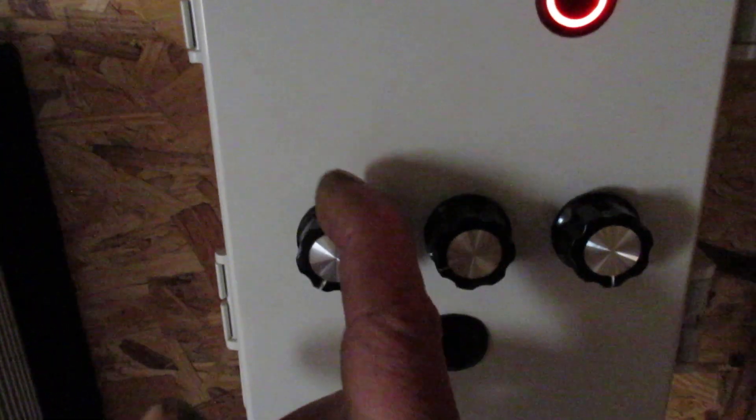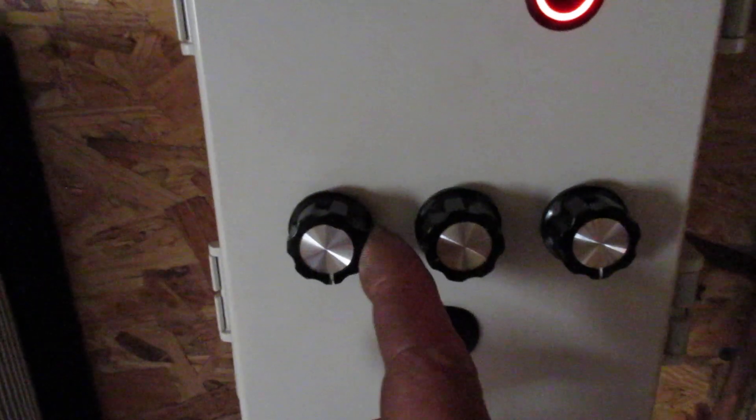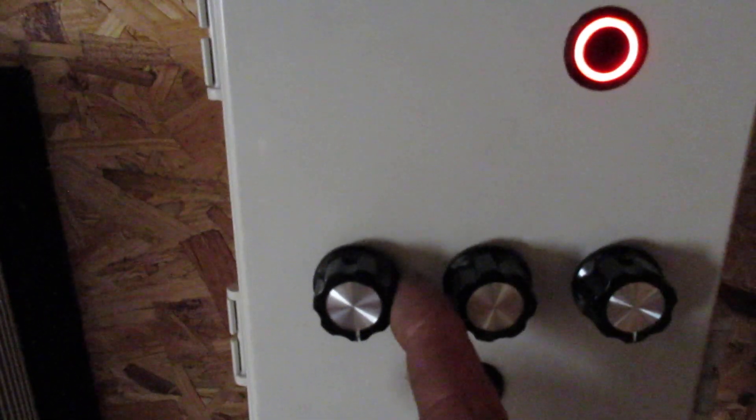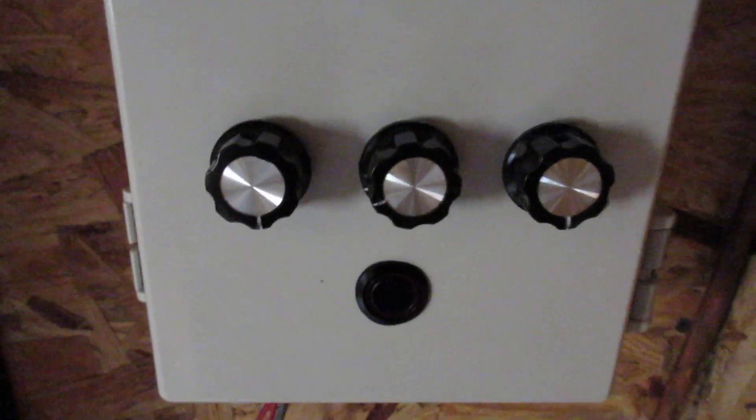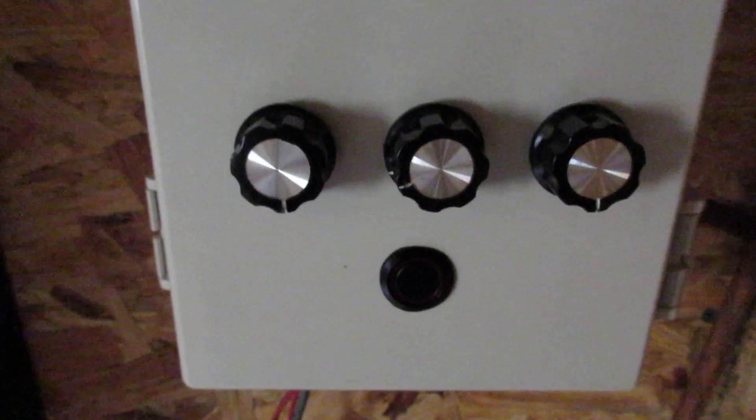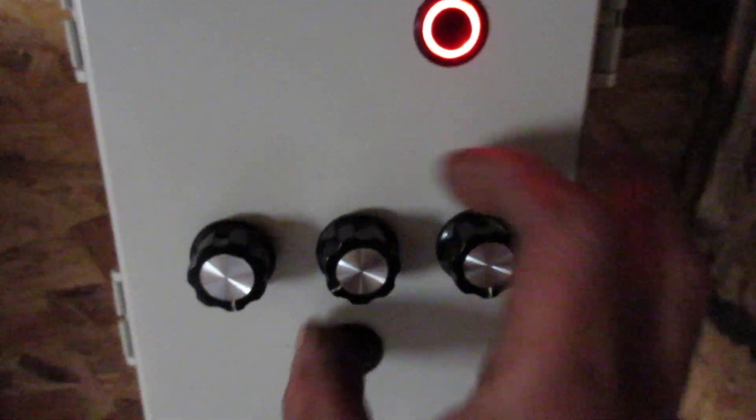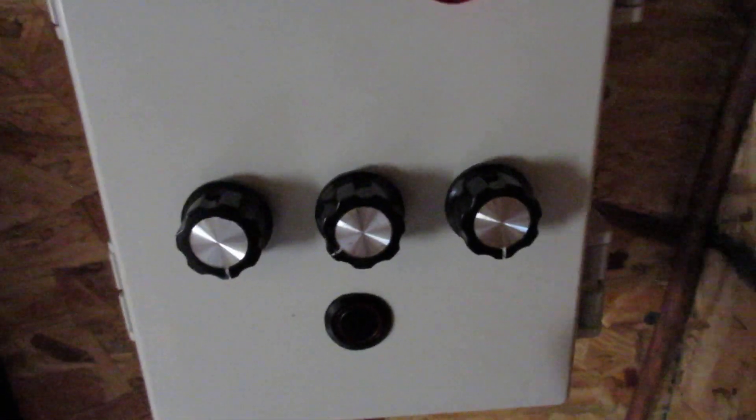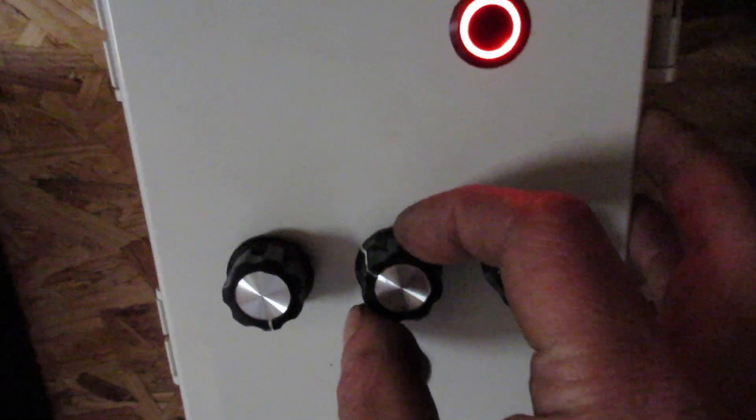But again, this one here is your choke position. So with this turned fully counterclockwise, the choke will be left fully open. So like in summer months, you may not even need to choke the generator, so you'll turn that all the way down. And then your duration - you could even shorten that. Winter months, you may need to lengthen your duration and of course go full choke.